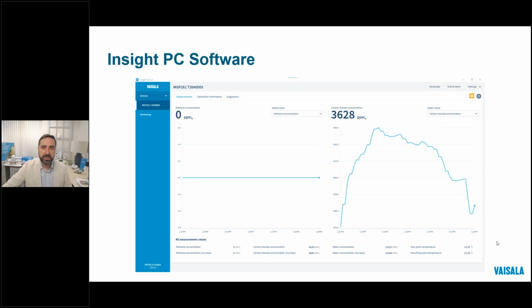Taking a quick look at the software, it provides an intuitive interface for viewing the outputs, troubleshooting, changing the configuration settings, or field calibration. You're able to edit the analog output scale, measurement settings, the ranges, signal and error limits, and customize the Modbus registers. And you can do any of this without fear of getting something wrong, since you can always revert back to the factory settings. The probes also store their own factory calibration information, as well as any errors and a history of exposure to extreme conditions. Our free tech support team can use this information to help quickly diagnose pretty much any issue you might have. Next, please.